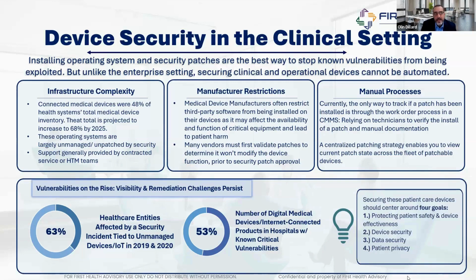Generally, the only way HTM has to track patching is through their CMMS. And of course, that requires it to be documented well and accurately. Even then, based on out-of-the-box work order configurations and trouble codes, it may be difficult to pull those statuses from within the language of work orders. We know a large amount of exploitable critical vulnerabilities affect medical devices due to the standard operating systems that they run on. And so patching processes for these systems that don't require software installation can save a significant amount of time and effort, and also provide a means to track and verify that the patches have been installed.